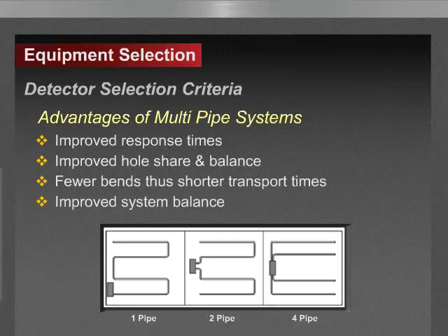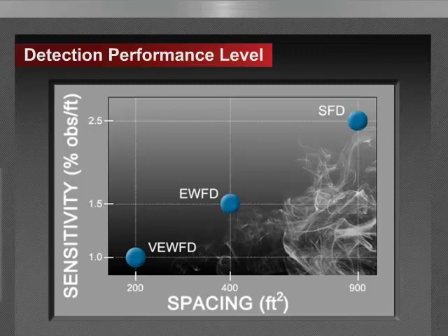Okay, great. This seems to be a follow-up to the question about spacing. The questioner says, I suspect that the previous question had to do with the requirement to derate spacing based on air velocity. If you look in NFPA 72, there are guidelines where there are higher airflows, and do ASD systems have to reduce the spacing based on airflows like spot detectors would?